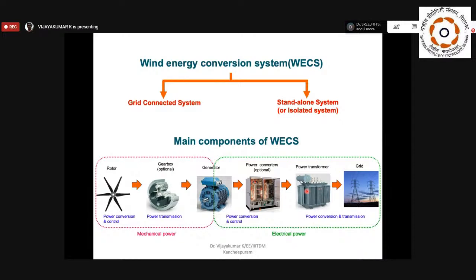Not only to match up the voltage, the power transformer will give great isolation between the grid and the wind turbine. So what's the purpose of isolation? This electrical isolation means if any fault happens in the grid, that won't affect your wind turbine. Or if you are having any fault with the wind turbine, that won't affect the grid. So it will provide great isolation between the grid and your wind turbine. So that's the purpose of using the power transformer here. So these are the main components in the wind energy conversion system.